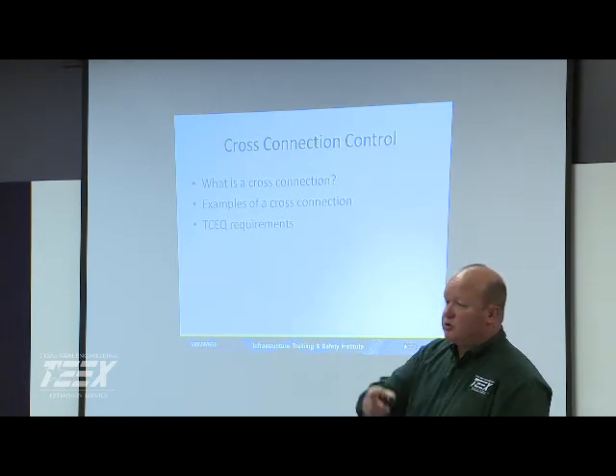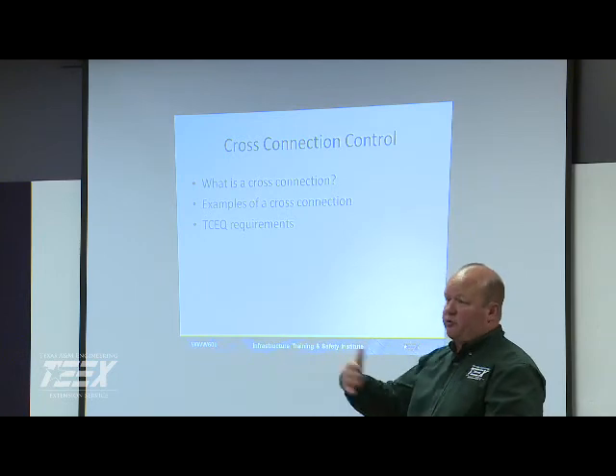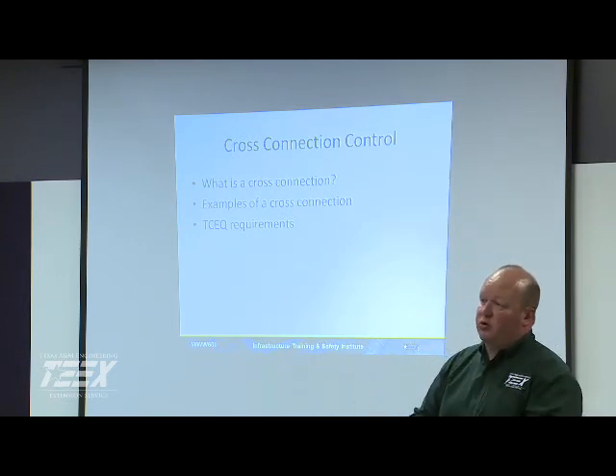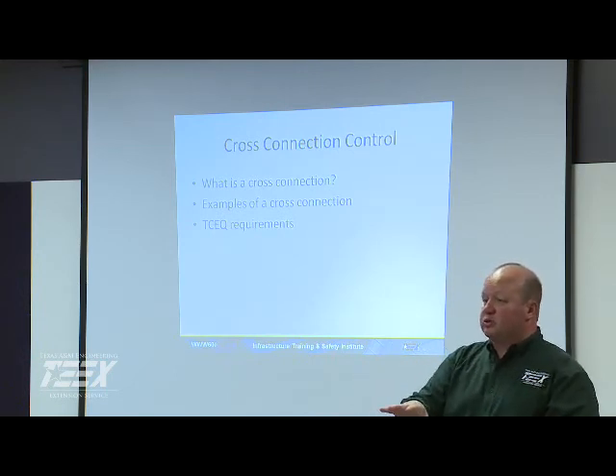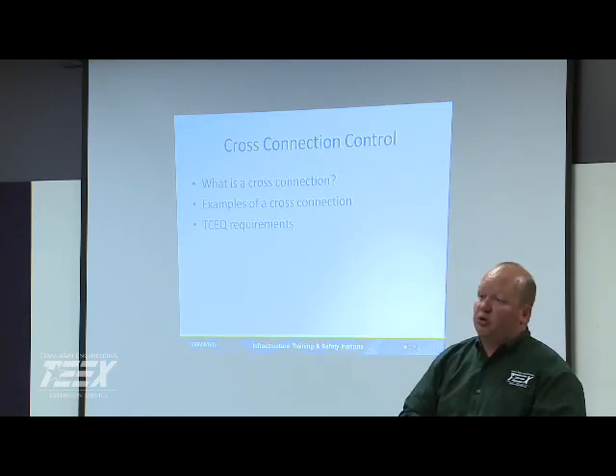So the most important thing, and we had an issue in San Antonio with it, is when you're having golf courses and you have somebody out there that's not familiar with the pipe, and they have a leak, and they're going to go and repair it. And that's where your cross-connection potential is. Yeah. So knowing who has recycled systems, and if you start having water quality issues out in that area, you know where to start looking.